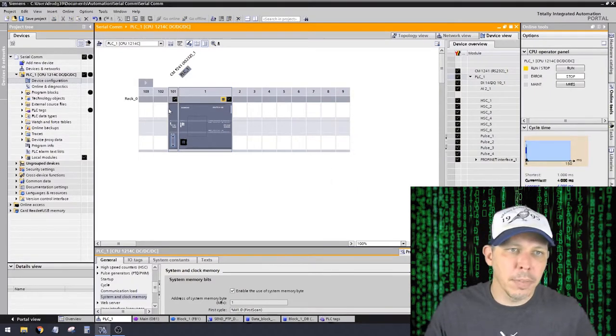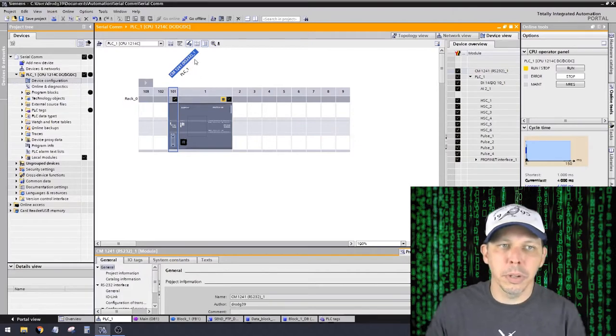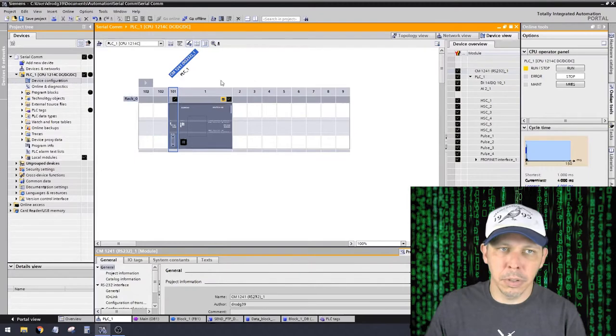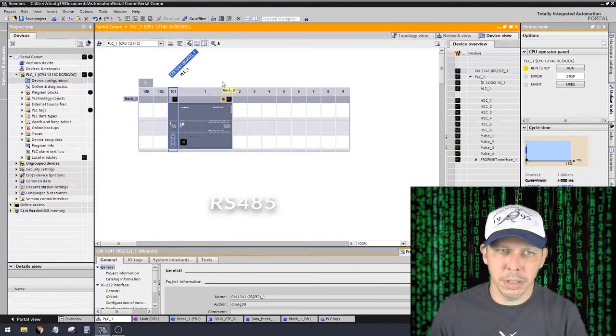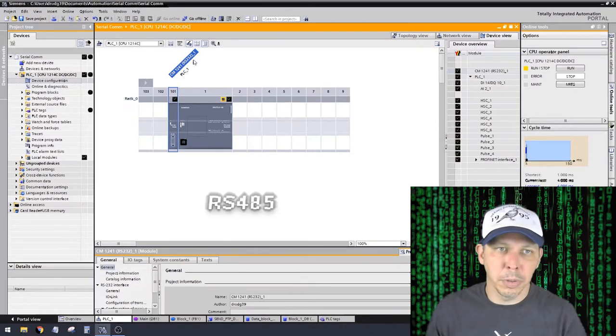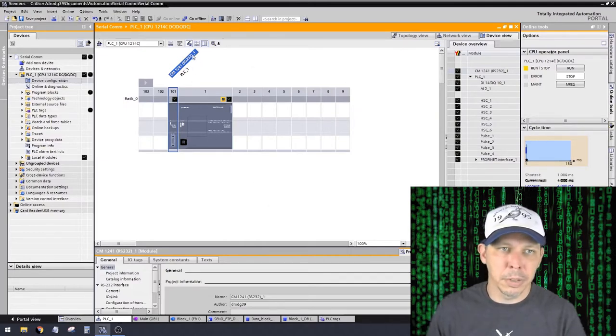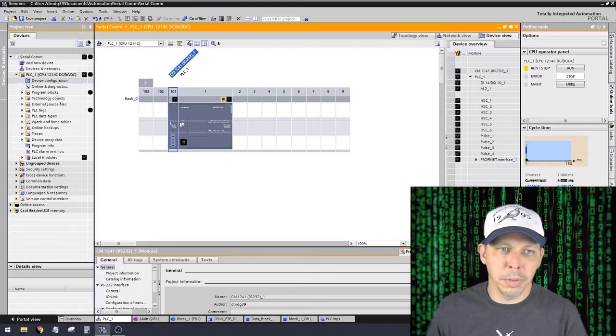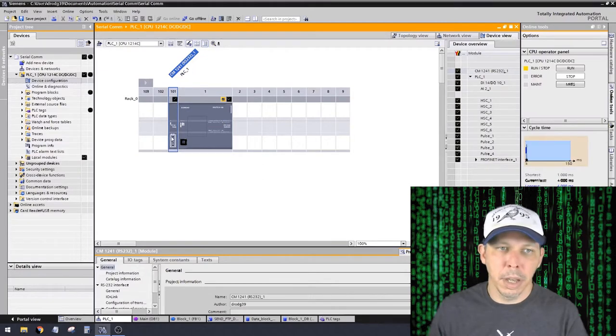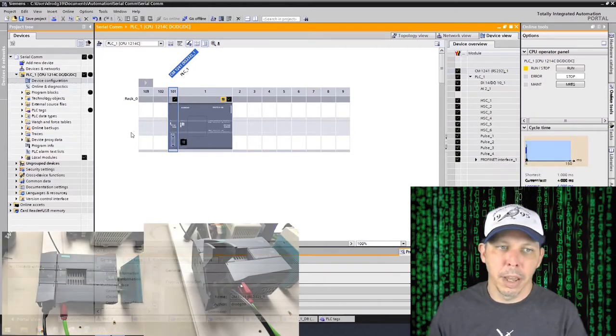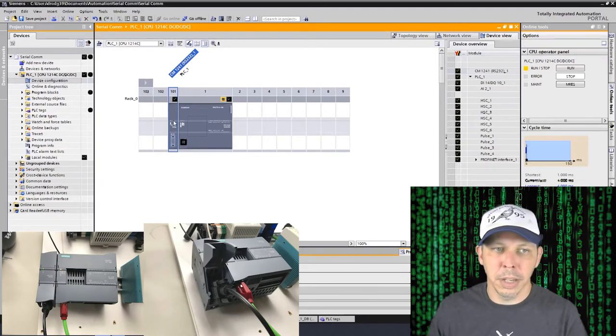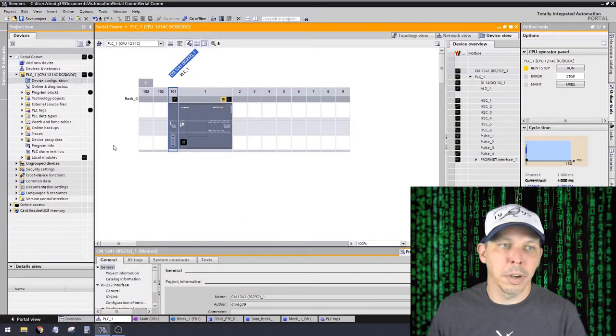And then I have the CM 1241 RS-232 module. So RS-232 is a serial communication standard. 232 is like the original serial communication. A lot of Allen Bradley's use 232. So we have this connected. It's a module that plugs into the side of the regular processor module and it has a 9-pin DB9 serial connector on the bottom of it. We have a serial cable coming out of it and I have that going into a computer so I can tell if I'm actually sending signals.